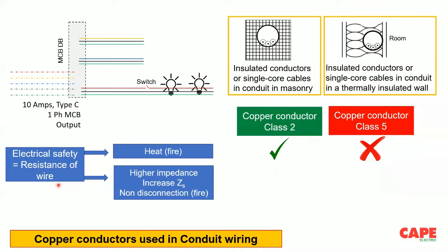Now, I am showing class 2 and class 5. Class 2 is a copper wire with lesser resistance, 8% or 9% lesser resistance. Class 5 is a copper conductor with higher resistance. This means class 5 wire with higher resistance is more dangerous in comparison to class 2 wire. All the calculations are made based on class 2 wire. All the conduit wirings we are supposed to make with a class 2 wire.